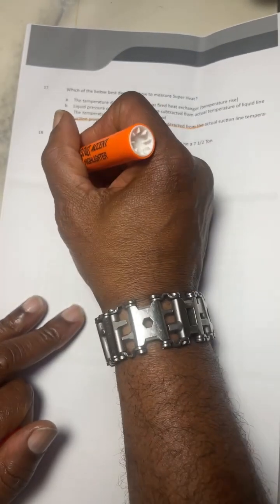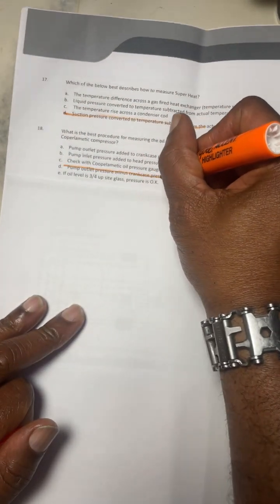A, the pump outlet pressure added to the crankcase pressure. B, pump inlet pressure added to head pressure. C, check with oil pressure gauge. D, pump outlet pressure minus crankcase pressure. Or E, if oil level is 3/4 up sight glass, pressure is okay. Now, I don't work on these, but I have the answer key. And number 18, the answer is D. Pump outlet pressure minus crankcase pressure.